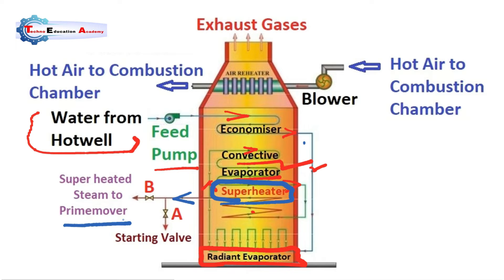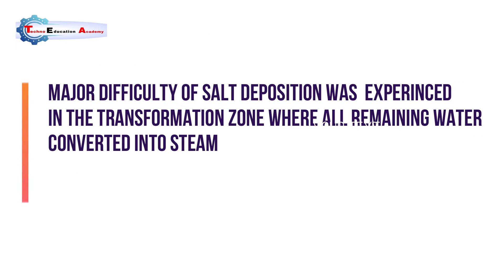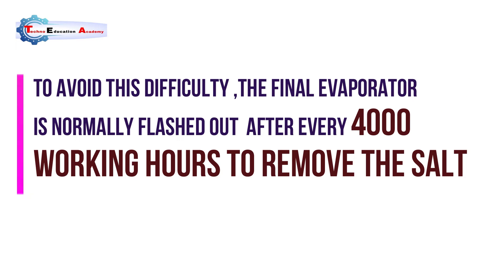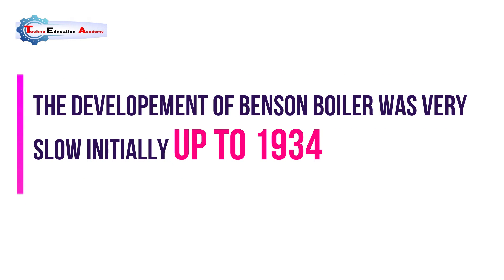A major difficulty of salt deposition was experienced in the transformation zone where all remaining water is converted into steam. To avoid this difficulty, the evaporator is normally flushed out after every 4000 working hours to remove the salt.